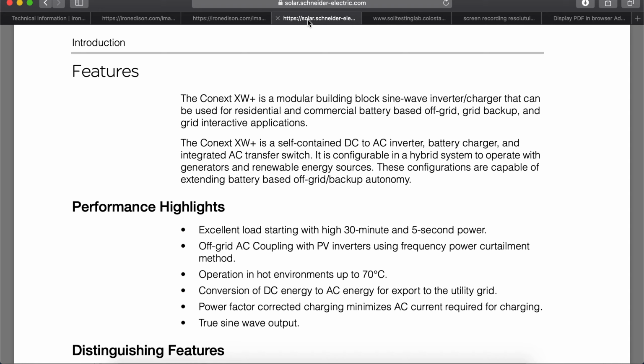Performance highlights: excellent load starting with high 30-minute and 5-second power. This is the surge rating. Off-grid AC coupling with PV inverters using frequency power curtailment method, also known as frequency shifting. Operation in hot environments, up to 70 degrees C. That's hot. Conversion of DC energy to AC energy for export to the utility grid. Selling back. Rolling that meter back. Power factor corrected charging minimizes AC current required for charging. True sine wave output.